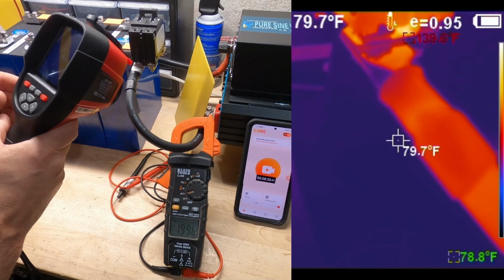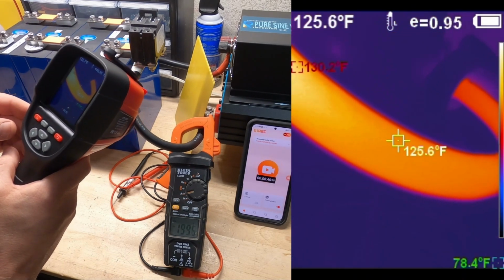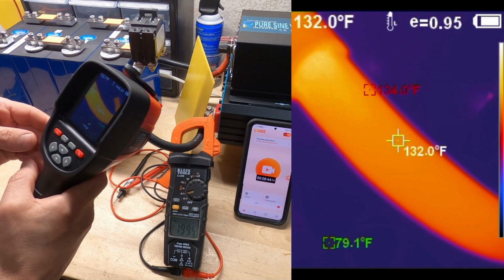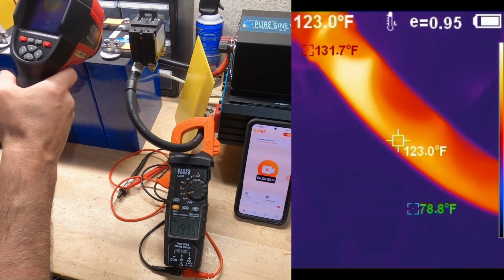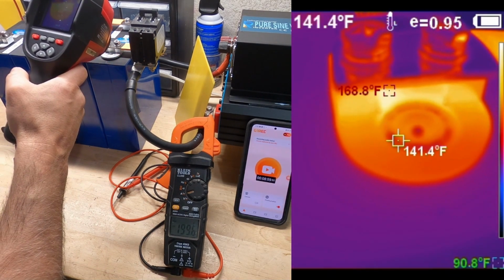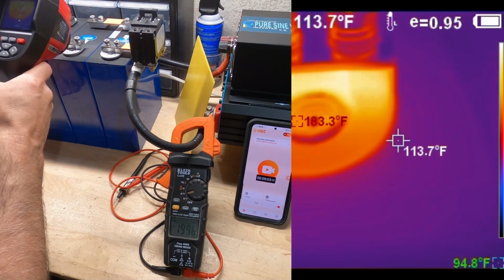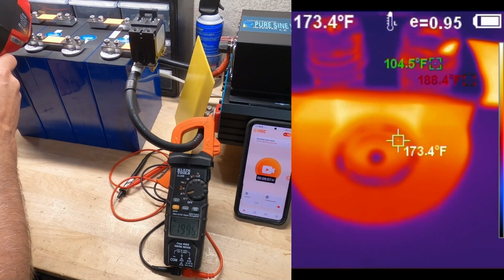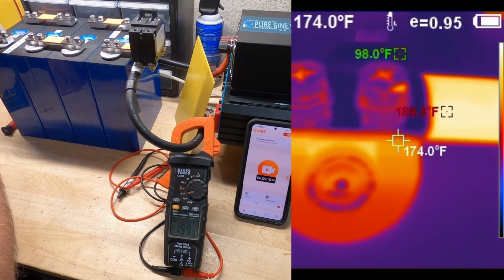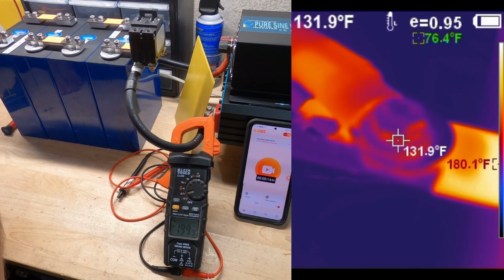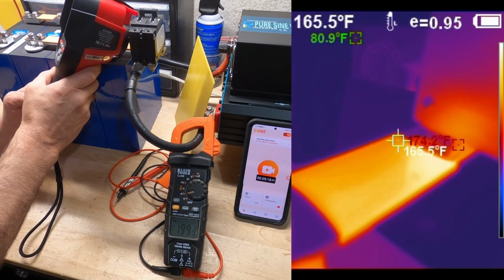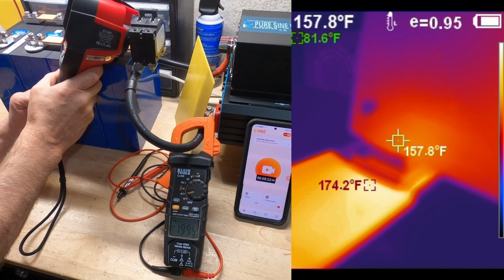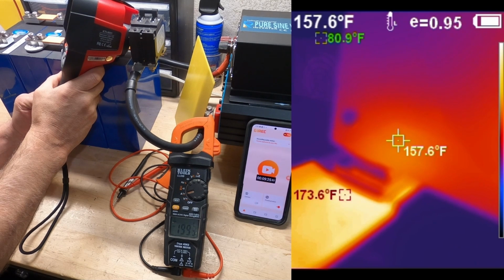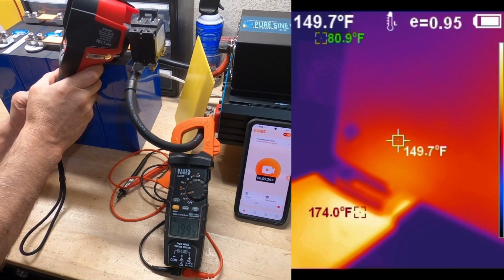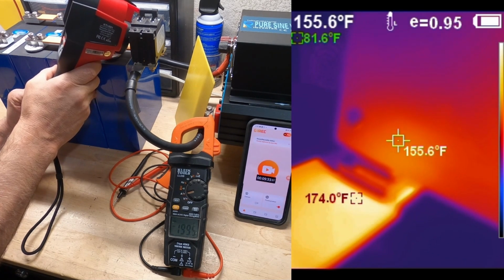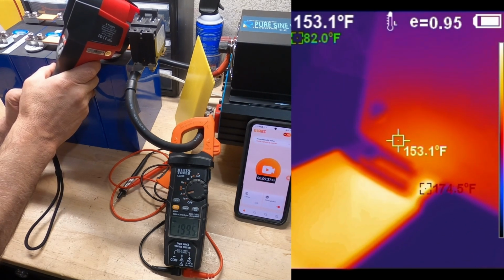Let's check our battery cable. So it has increased about 30 degrees up to about 130 degrees on the cable itself. It's not as hot as the bus bars. These bus bars and the studs still 160, 170 degrees. That one I saw 180 a minute ago. Let's check the terminal on the breaker. So the breaker's gotten up to 160 degrees. That's pretty warm. I don't like anything to be over 140 degrees. But it hasn't tripped.